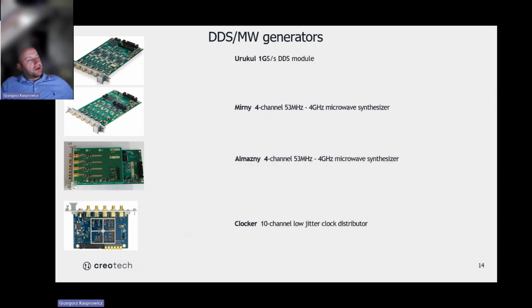Then we have generators. For the moment we have Urukul, which is a 1 gigasample DDS, a quad 4-channel DDS module, which has very good specs. It's very well characterized. It's very low noise. It's mainly used for lasers, for AOM driving. It has two flavors. One is 9910, another is 9912. They have slightly different characteristics. One of them is able to synchronize not only channels in a module, but you can also synchronize multiple channels in the crate.